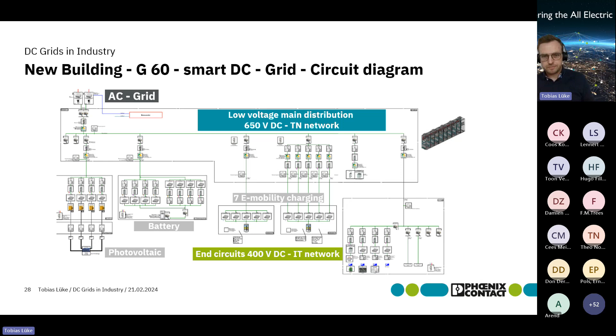This is supported by four times 30 kilowatt DC-DC converters, which are connected to the PV. We have the battery energy storage for charging and discharging, our e-mobility charging stations, and our end circuits like lights, building automation, and all the 24 volt appliances, which we call end circuits, running on the 400 volt DC IT network. And of course the machine itself will be connected directly to our 600 volt DC grid, so all the heavy loads within the machine, in order to investigate the effect of recuperation.